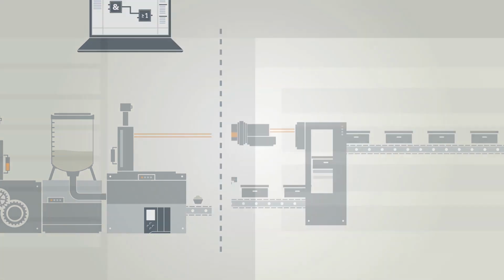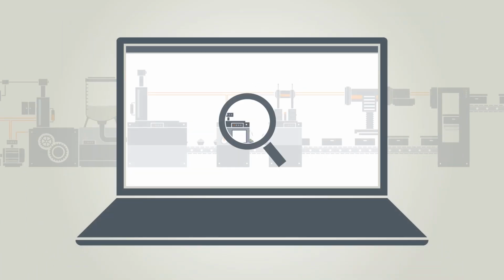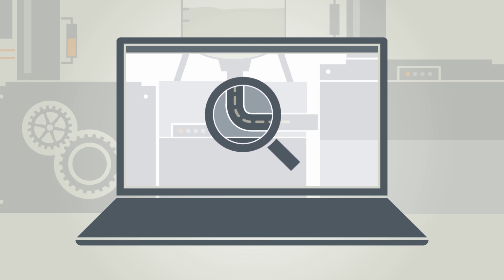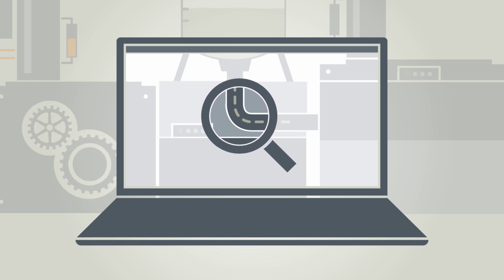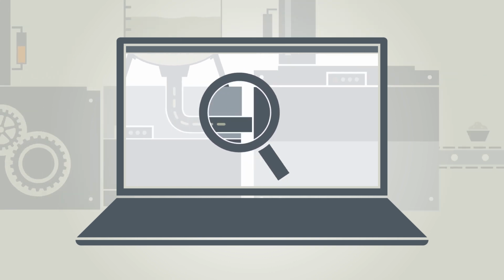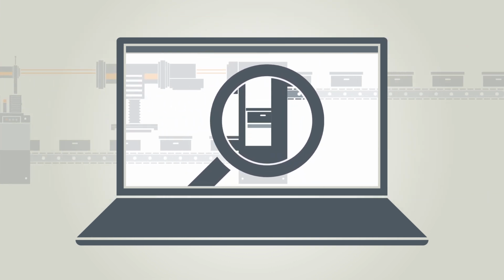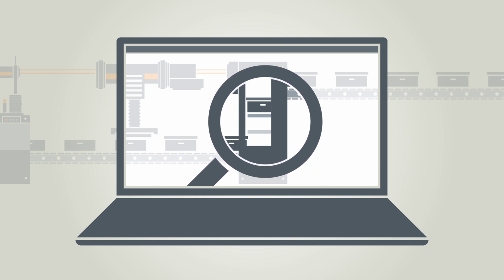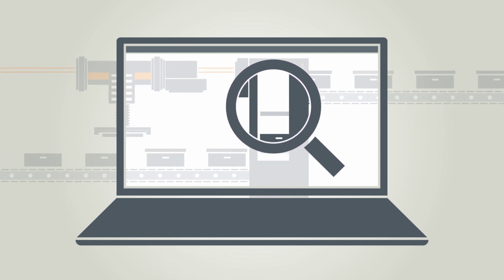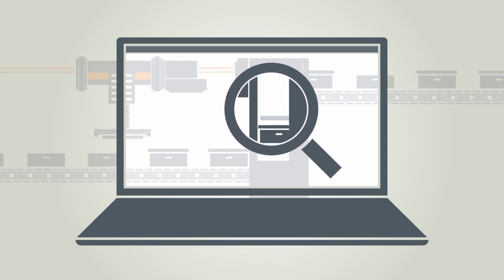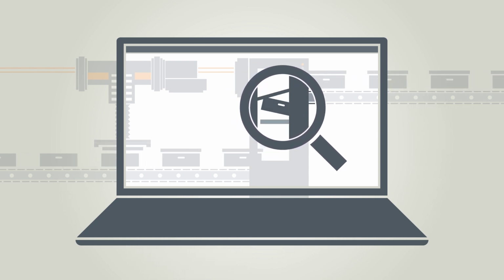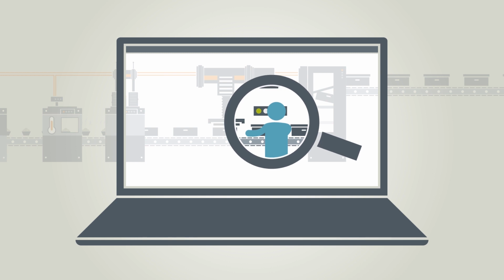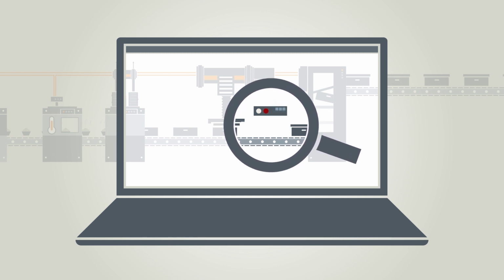For supervision, you have a choice of various types of supervision in the TIA portal. With operand supervision, you primarily monitor static signals, such as pressure and control supply voltage. Interlock supervision keeps track of whether the necessary releases exist for the movement, such as whether the protective door is closed. Action and reaction supervision monitors whether a movement has started or stopped as desired. Position supervision monitors the status in an idle state, thus whether an object has changed its position unplanned.